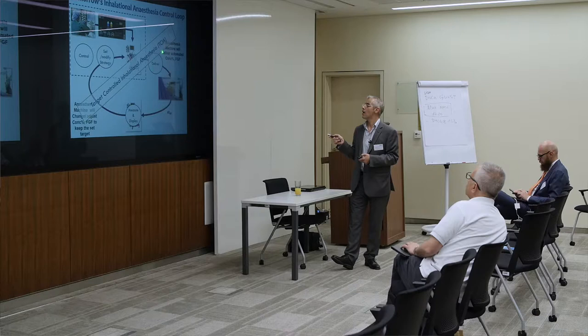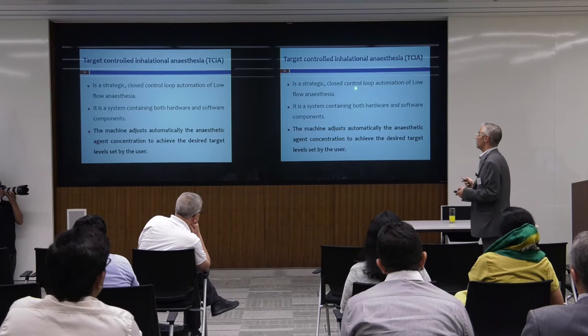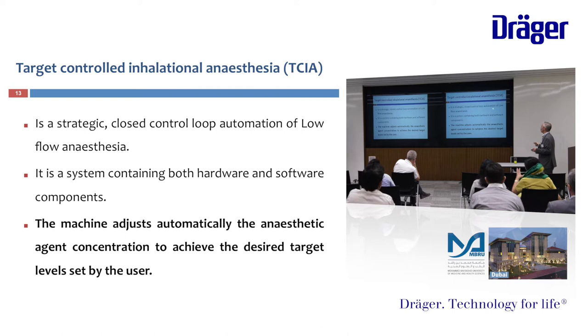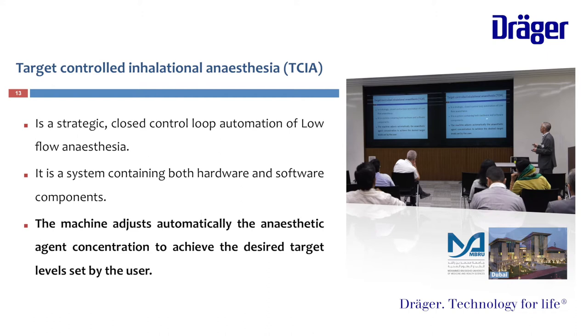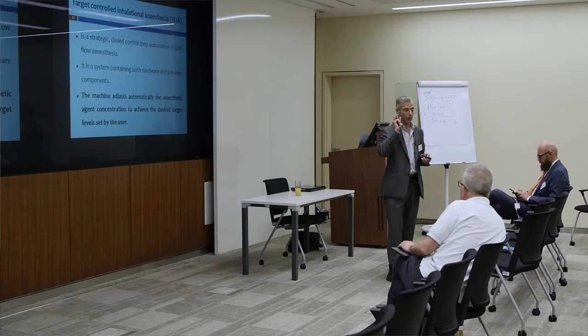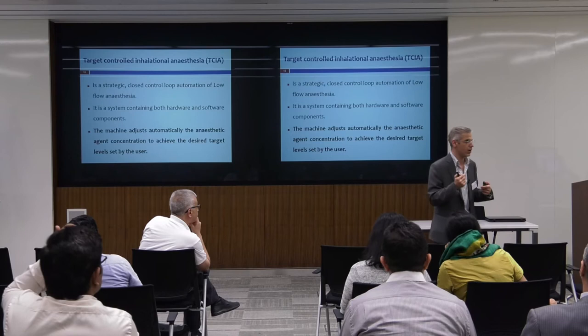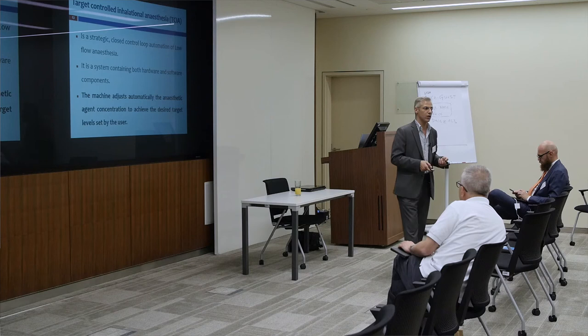We can do this by target-controlled inhalational anesthesia. What are the benefits? Why do we need it? Target-controlled inhalational anesthesia is a strategic closed control loop automation of low-flow anesthesia. It is a system containing both hardware and software. The machine adjusts automatically the anesthetic agent concentration to achieve the desired target level set by the user. All we need to do is adjust the end-tidal volatile anesthetic that we need and let the machine do it automatically.